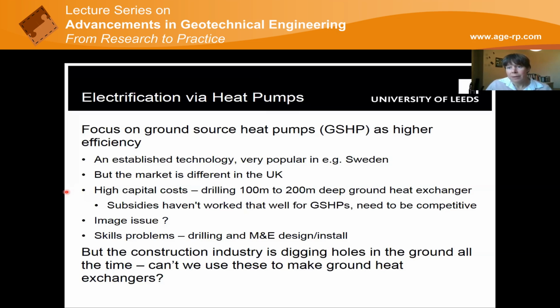In some parts of the world it's a very established technology, particularly in Scandinavia, but in the UK we've struggled to really get significant ground source heat pump systems off the ground. The capital cost of drilling deep boreholes has been one issue, and we haven't quite got subsidies right to increase competitiveness. In the early days of installing these systems in the UK, the skills in the market perhaps weren't sufficient, leading to an image problem from schemes not working as well as they should have. And if we're really going to hit the millions of ground source heat pump systems we need, we probably don't have enough drillers or drill rigs.